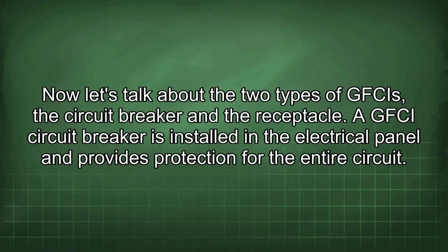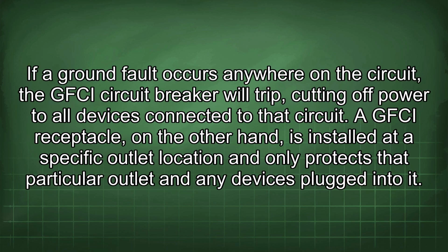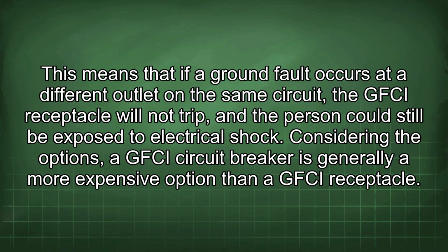Now let's talk about the two types of GFCIs, the circuit breaker and the receptacle. A GFCI circuit breaker is installed in the electrical panel and provides protection for the entire circuit. If a ground fault occurs anywhere on the circuit, the GFCI circuit breaker will trip, cutting off power to all devices connected to the circuit. A GFCI receptacle, on the other hand, is installed at a specific outlet location and only protects that particular outlet and any devices plugged into it. This means that if a ground fault occurs at a different outlet on the same circuit, the GFCI receptacle will not trip, and the person could still be exposed to electrical shock.